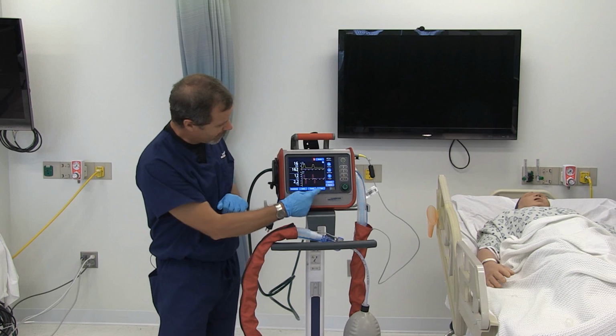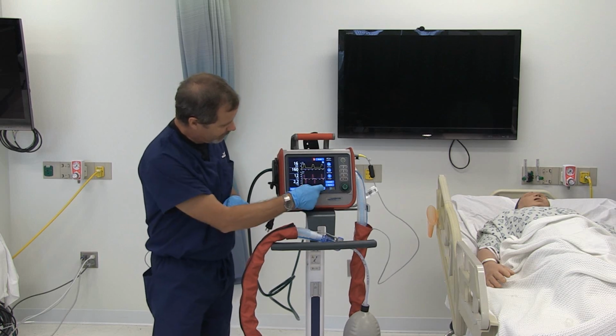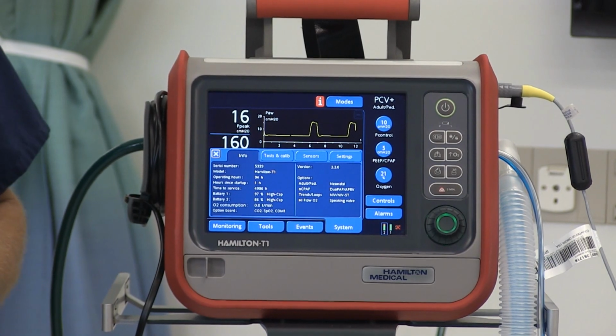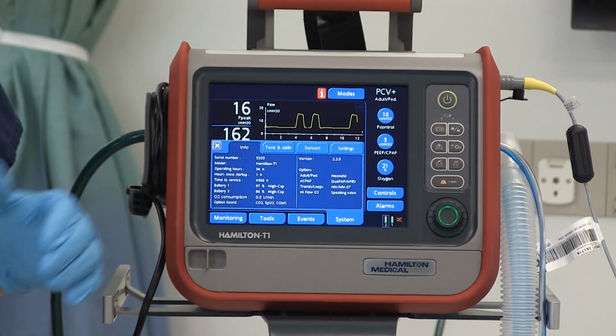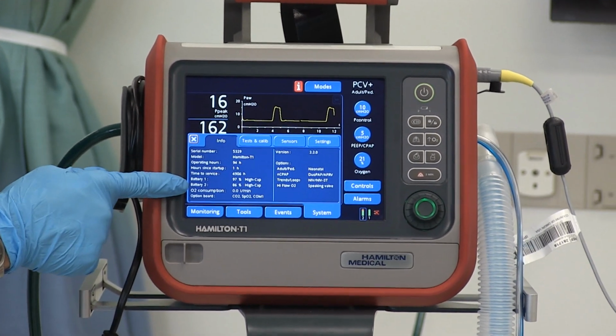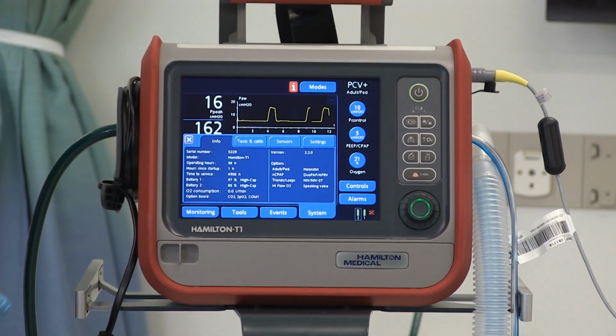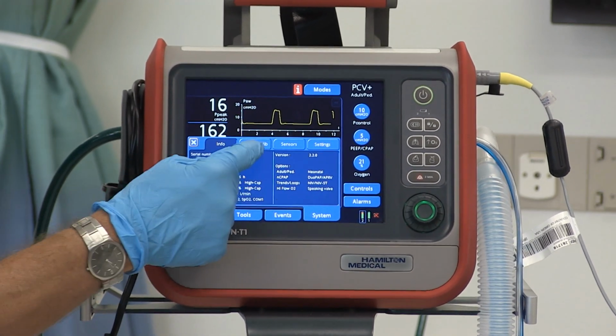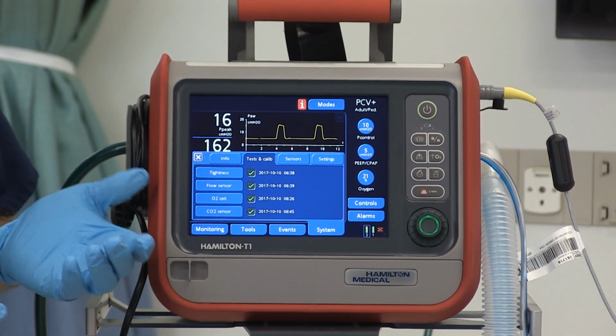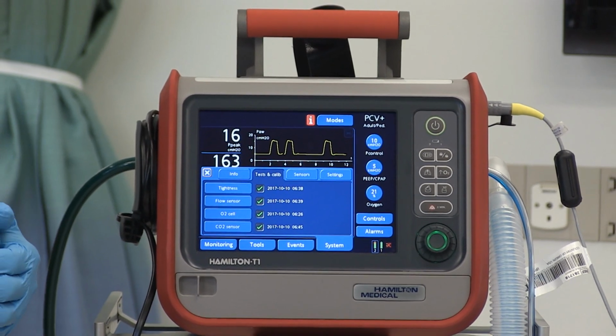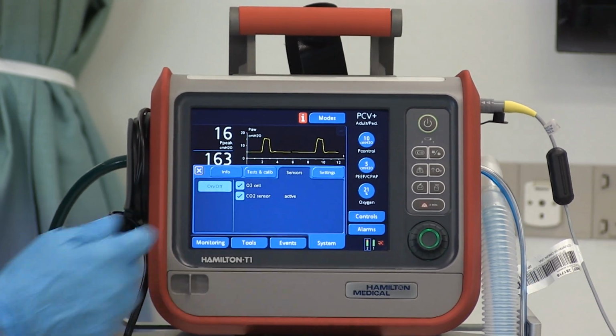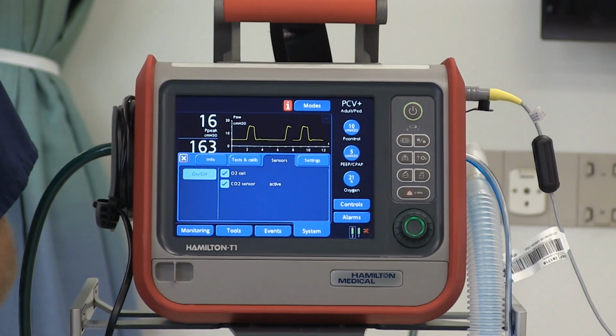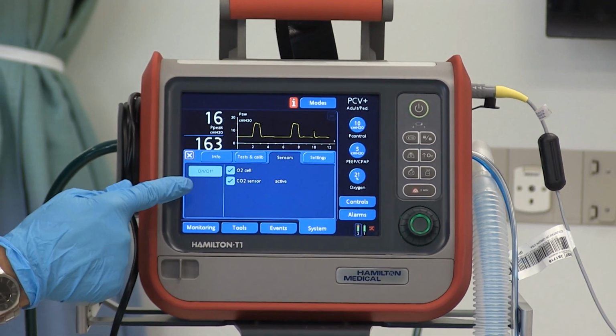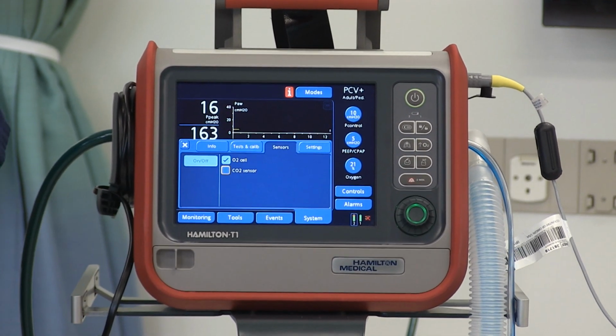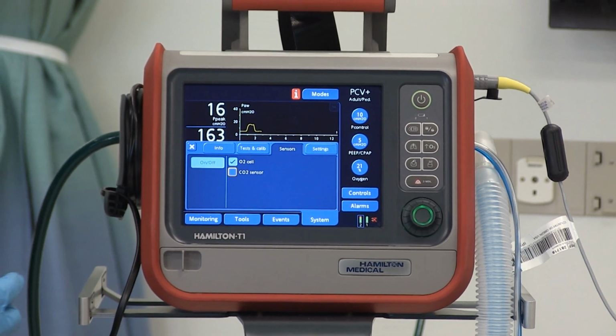Okay, coming across the bottom, System tab. We can see various information such as the serial number, the O2 consumption in liters per minute, little bits of information like that. Next tab over is, now we're back to that test and calibration window that we saw earlier. Sensors on off. If I were to want to deactivate a certain sensor, such as the end-tidal CO2, I just tap the box and it's deactivated.